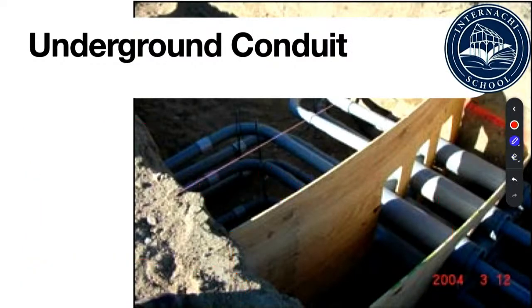This is a commercial property, and they were using a lot of PVC for the conduit. And what's nice about the PVC underground is that it doesn't rust, it doesn't corrode, it doesn't rot, basically, which is cool. That's always a good bonus. But the bad thing about it is it also doesn't conduct electricity. So in conduit systems, we actually use the conduit itself for our grounding system so that it actually gets energized if I have a ground fault that happens. So whenever I'm dealing with PVC conduit, since it does not conduct electricity, I still have to pull a ground wire inside this conduit. I can't just pull my normal wires as I normally would.